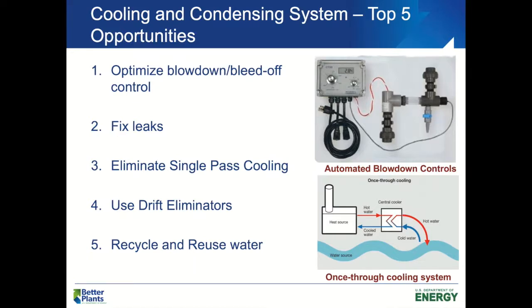So the fourth one I have here is again associated with cooling towers. Drift eliminators are kind of like additional panels that you can add on to your cooling towers. Most modern cooling towers come with these drift eliminators. What they essentially do is decrease the water droplets from escaping with evaporation, reducing the losses associated with the cooling tower itself.